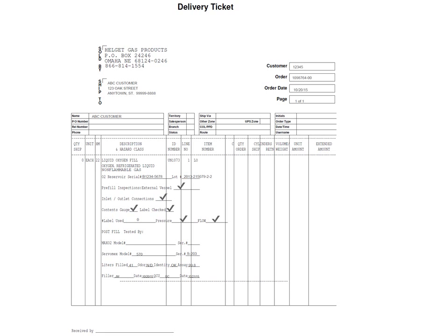You will document your pressure that's on the reservoir and the flow. I refer you back to your standard operating procedures. There is an operating procedure that goes through step by step exactly how to fill a liquid oxygen reservoir. This is just an overview.